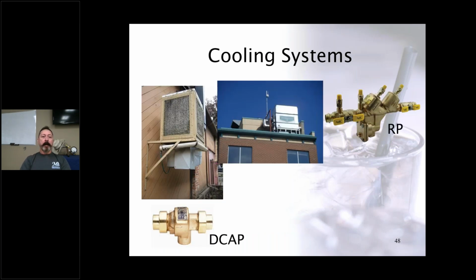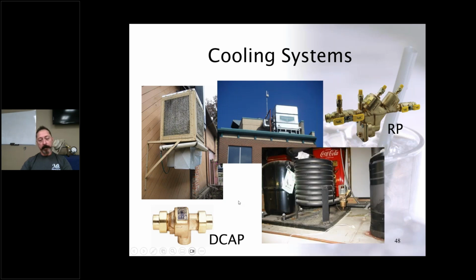Cooling systems can be somewhat hazardous because they'll use cooling and heating mediums. That's a swamp cooler there. It drains, keeps straw moist, and you can have bacteriological buildup of different types of airborne contaminants, Legionnaire's disease, for example, and we don't want that in a drinking water supply. So typically that would be an RP backflow preventer, which stands for reduced pressure principle, or for low hazard cooling systems, a dual check with atmospheric port. So there are different types of backflow preventers for different applications and different hazard levels.